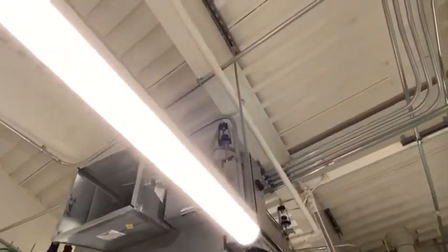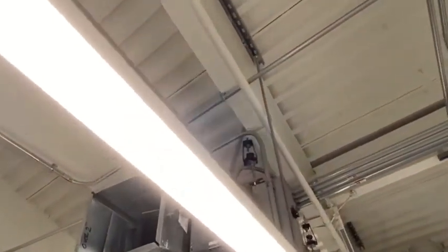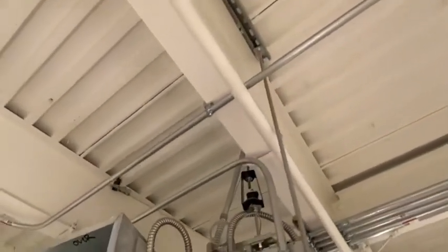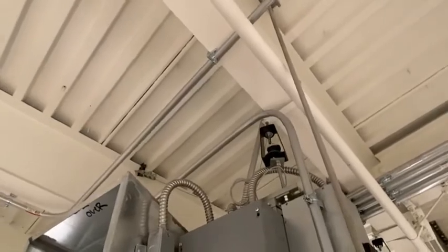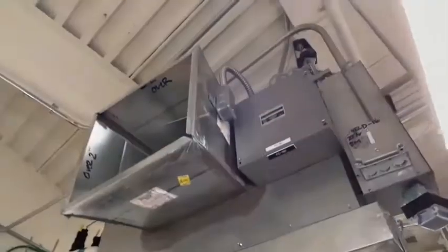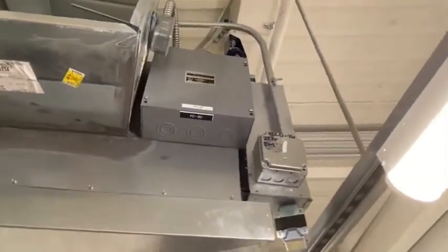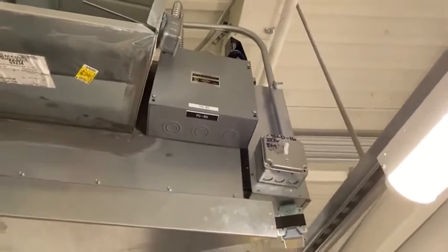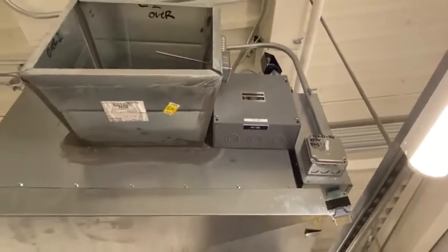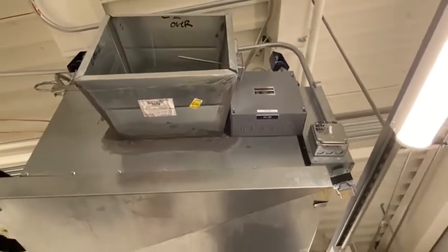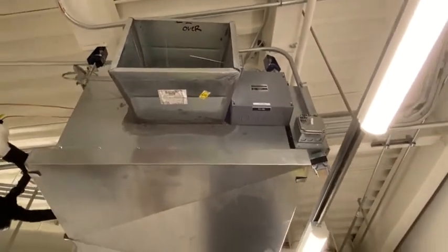It's like a residential disconnect switch on an air conditioning unit right here, okay? And then that way the unit will be powered. Once you put that back in, you'll have to flip the switch on, and you'll have power through the unit to do your voltage testing. Anytime you're doing live electrical work, make sure you follow Cal Poly Pomona's proper arc flash procedure and voltage checking procedures, okay?